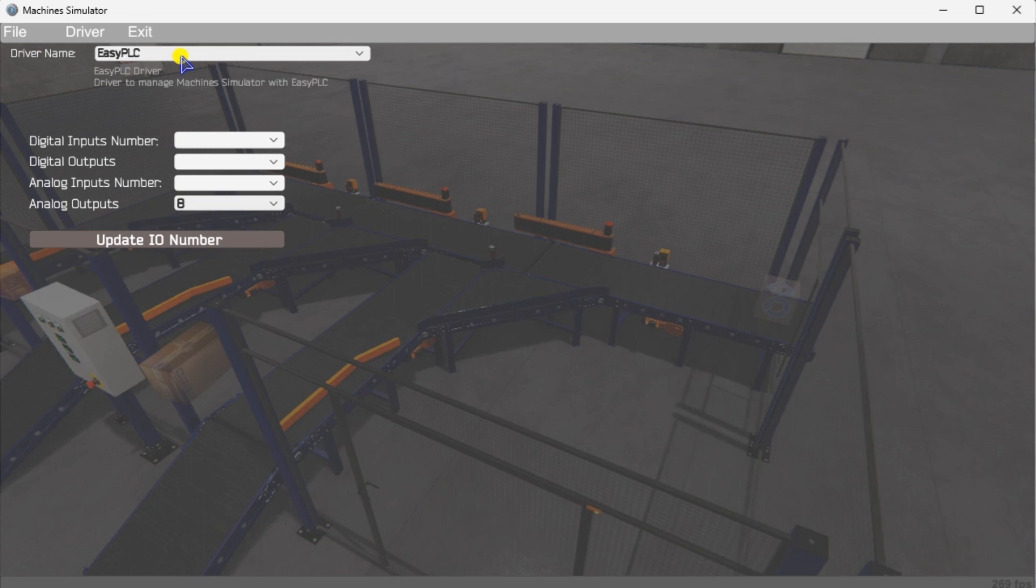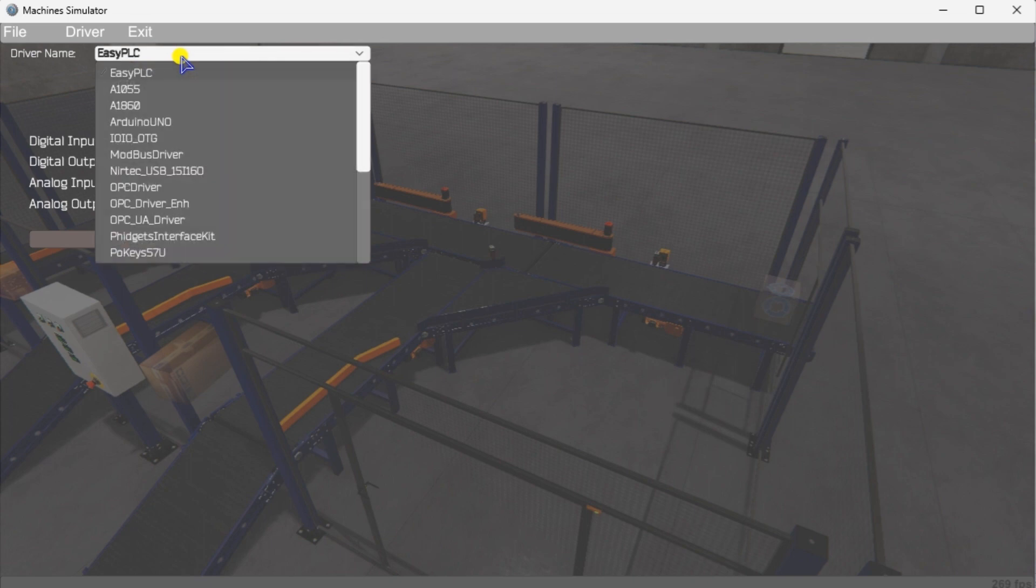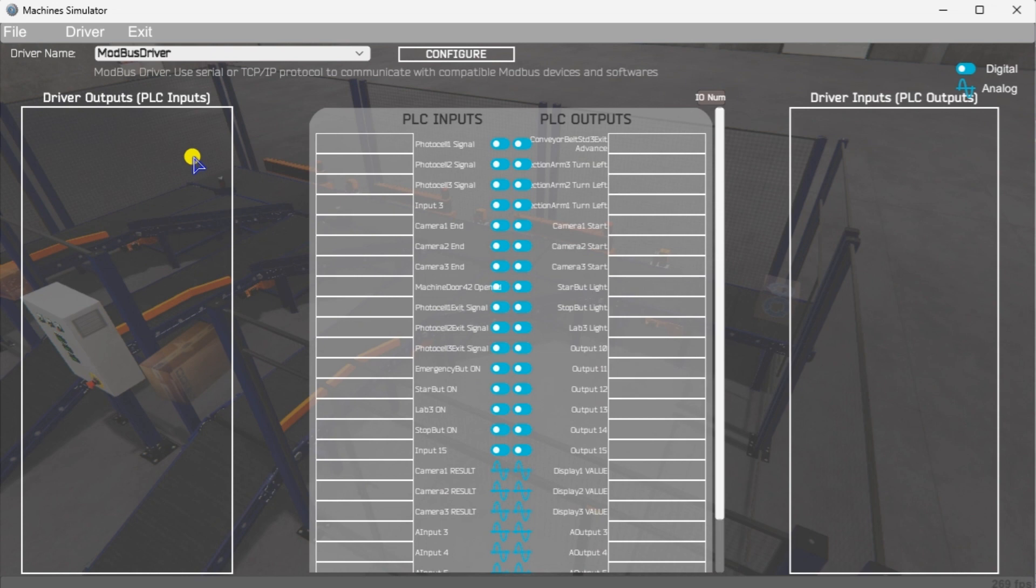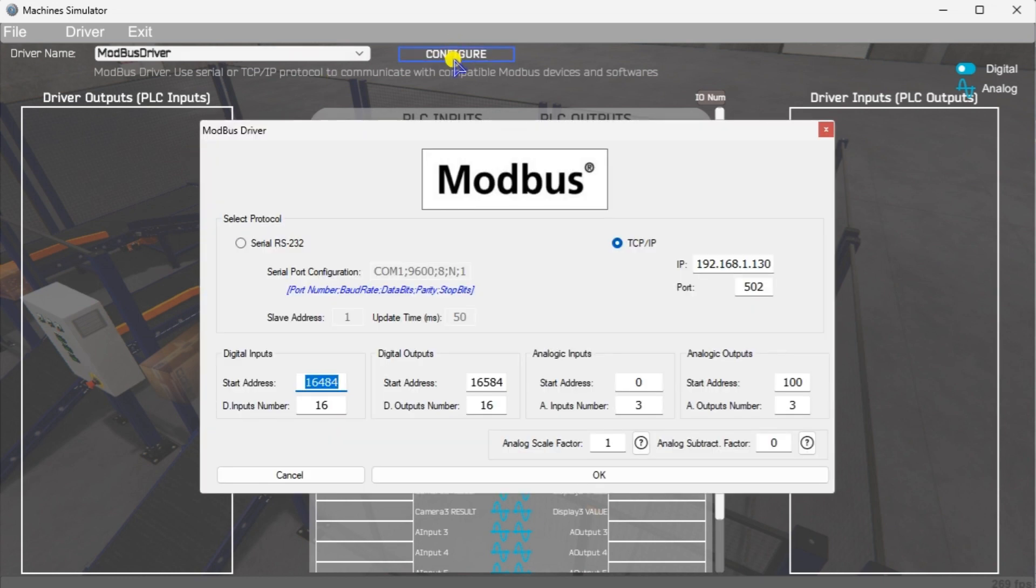Under the driver name, pull down menu, select Modbus Driver. This driver will communicate Modbus TCP Ethernet and Modbus RTU Serial. Select the Configure button. We can now enter the information for our Modbus driver. Select TCP IP. This means the computer's Ethernet port will communicate to the PLC.